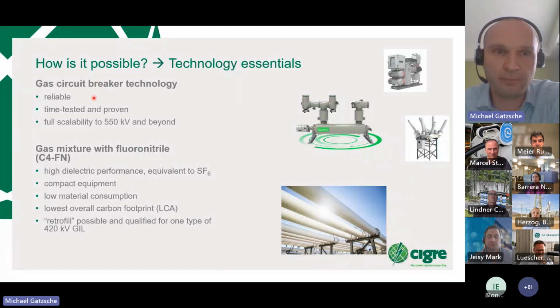The gas circuit breaker technology is time-tested, proven, and reliable—we have decades of experience with SF6. The scalability is proven, and we're developing up to 550 kV now, but we can go beyond; there's no limit in scalability. When we look at SF6-free technologies for breakers, the gas circuit breaker technology is the only one proven for 420 kV—for example, vacuum doesn't have this option yet at 420.